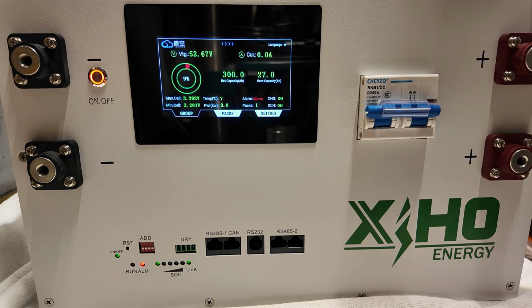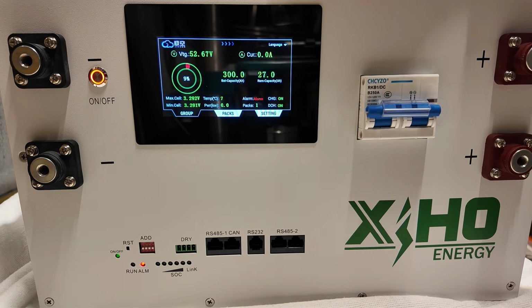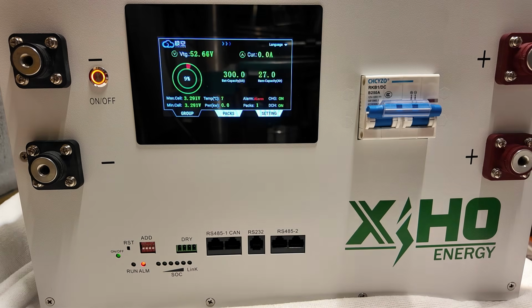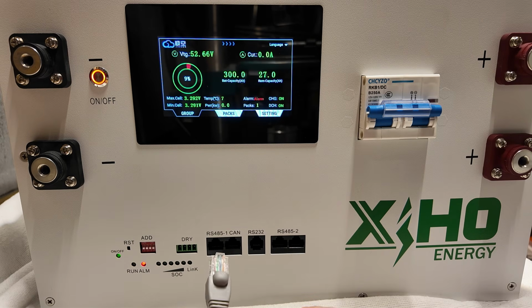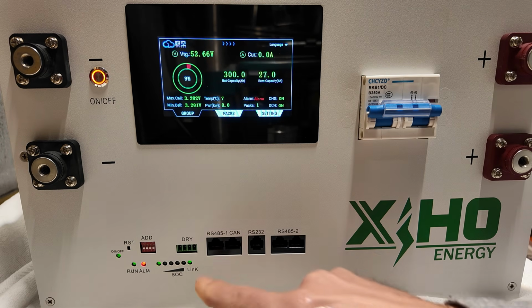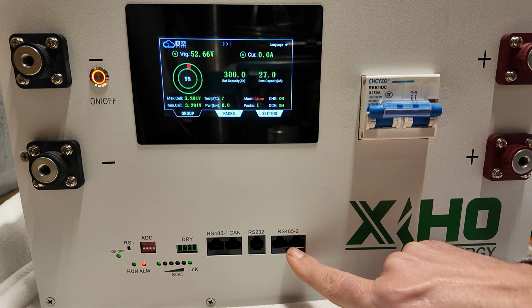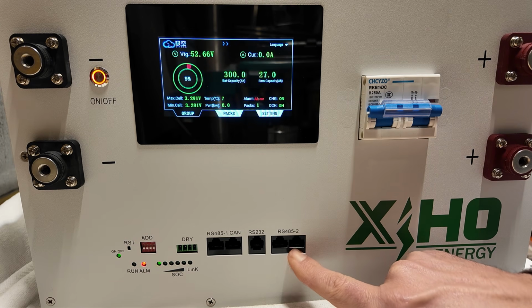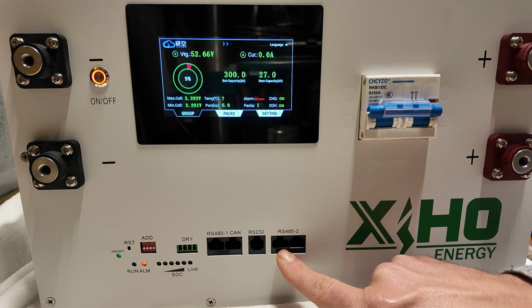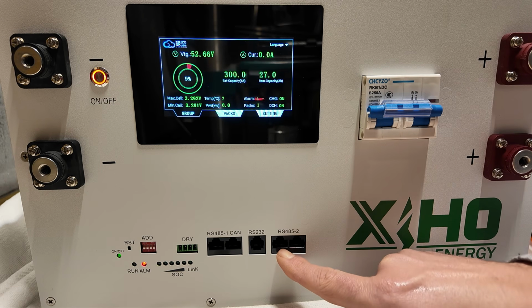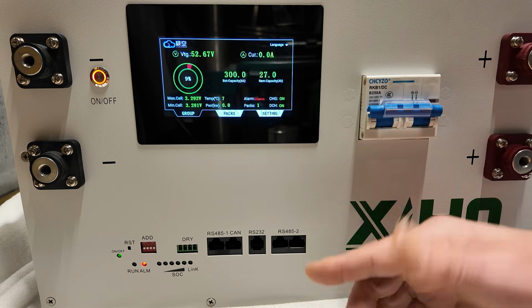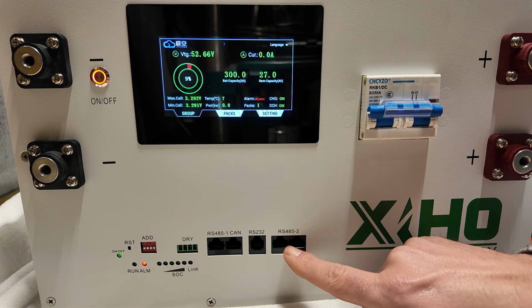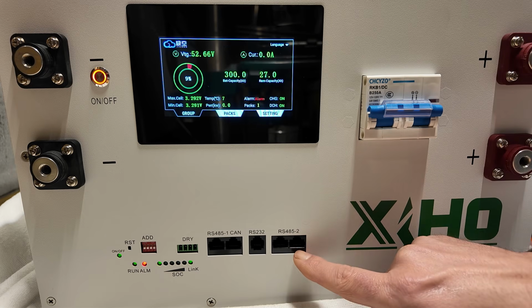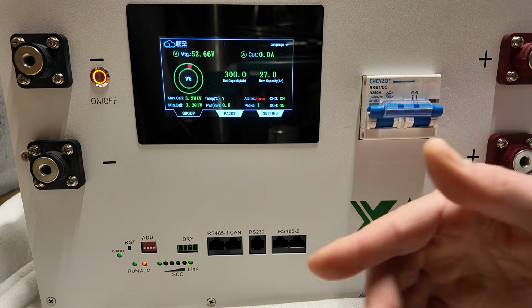We're back in the shed and let's connect our battery with RS-485 and personal computer. We already installed the software, now we have to connect the battery with the computer. Now we have to decide in which port we have to connect the UTP cable. We have 5 ports. At the right we have the RS-485-2. This port is used to interconnect multiple batteries. If you want to stack them, if you want to daisy chain these batteries, you have to use these ports and use a regular UTP cable to connect battery 1 with battery 2 with battery 3.